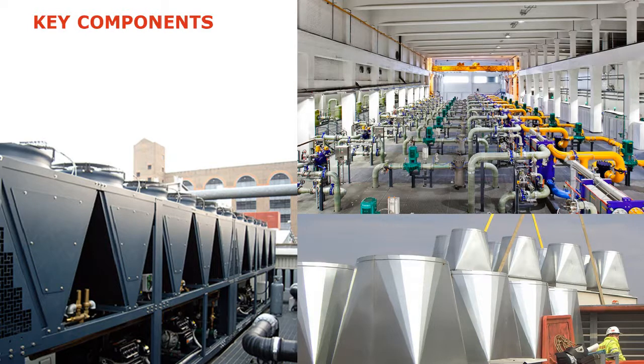Another key point was that the power densities in those days were very much lower than they are now. I think we were typically expecting around 300 watts per rack, a third of a kilowatt a rack. A rack typically is, for those that aren't familiar with the terms in the industry, basically a metal cabinet which houses all of the computer equipment, typically about 600 millimeters by about a meter, 1.2 meters, something like that. Takes up roughly about 2 square meters of floor space. So quite a low power density. That's what we were trying to build for in those days.